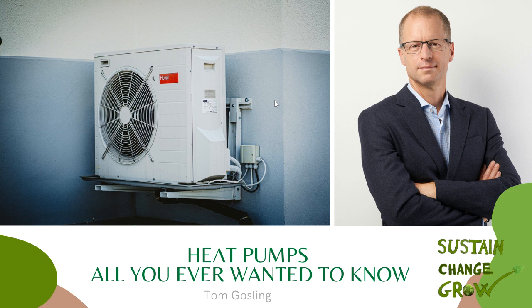A ground source heat pump gathers energy out of the earth. You dig a borehole, and you have your heat exchanger operating in a way that gathers heat out of the ground. The advantage of that is that the heat of the ground is much, much more consistent around the year. So even if it's got to -4 degrees in the air, if you've drilled, I don't know, 30 meters down, actually they don't go that deep, but if you go 10 meters down, let's say, then it might well be 12 degrees at that point.